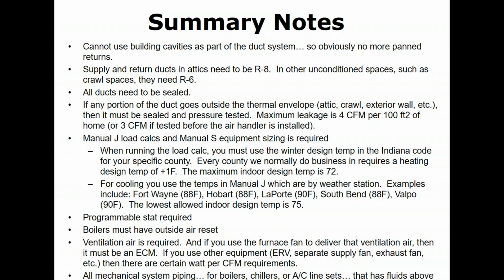That's no longer allowed. You can't put a piece of foil panning or metal panning on the bottom joist in the basement and use the two studs and the floor as the other sides of the duct. Not allowed. It's got to be all fully ducted. I mentioned you got to insulate ducts when they go outside the thermal envelope. So attics are R-8, other spaces are R-6. All ducts have to be sealed.